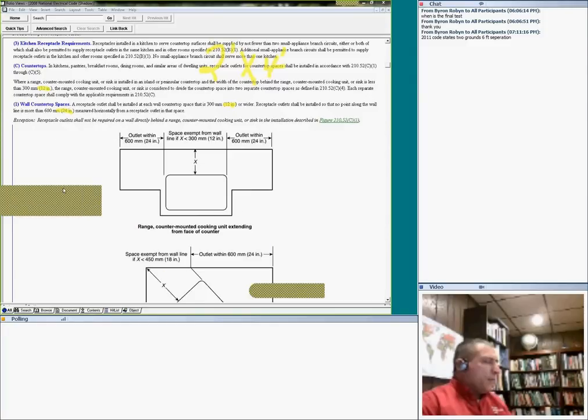The journeyman exam, this particular one, guys, look at this one. It's exempt from the wall line if it's less than 12, please remember this for your journeyman exam. If it's less than 12, and if it's kitty corner like this, if it's less than 18. What does it mean? If the space in the exam is right at 12, they see the distance here is 12, then you start placing your receptacle. You go here, you place your first receptacle, that's your 2 feet. And then if it's 12, you continue out here and put your second receptacle. That's 4 feet. And you keep going here, and up to here.